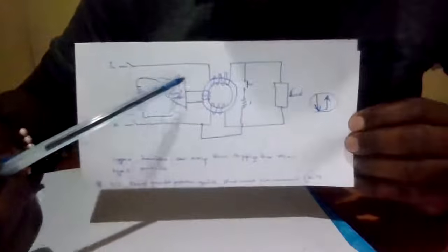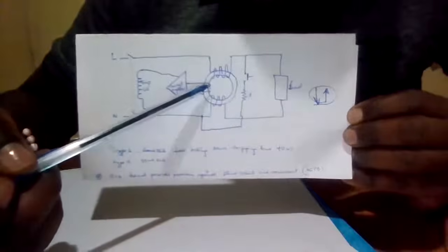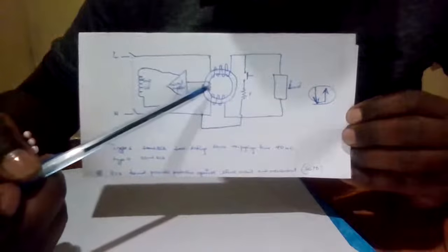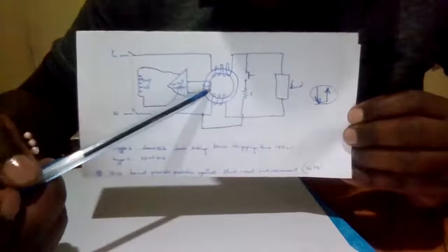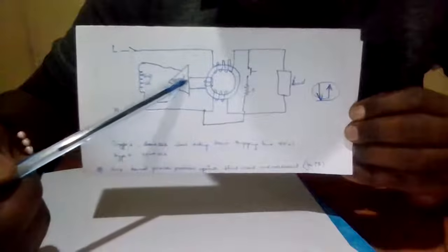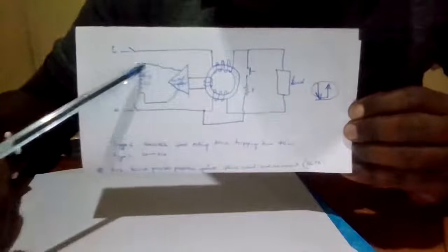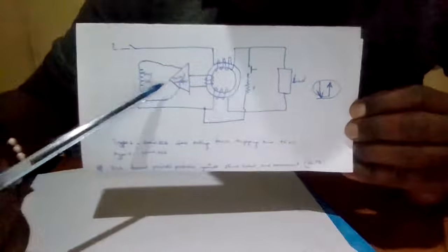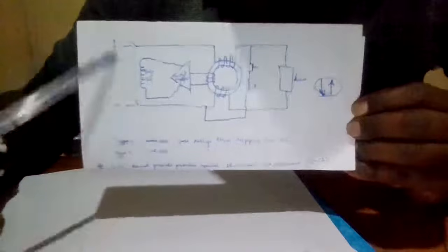But now, what will happen when there is an imbalance in the neutral? There is a production of a rotating magnetic flux in this toroid. So we have to add a search coil, which is this one. This coil will sense the current, and we amplify it so that it is enough, based on the calculation, to energize this tripping coil to trip the device and cut the circuit. That is how it works.